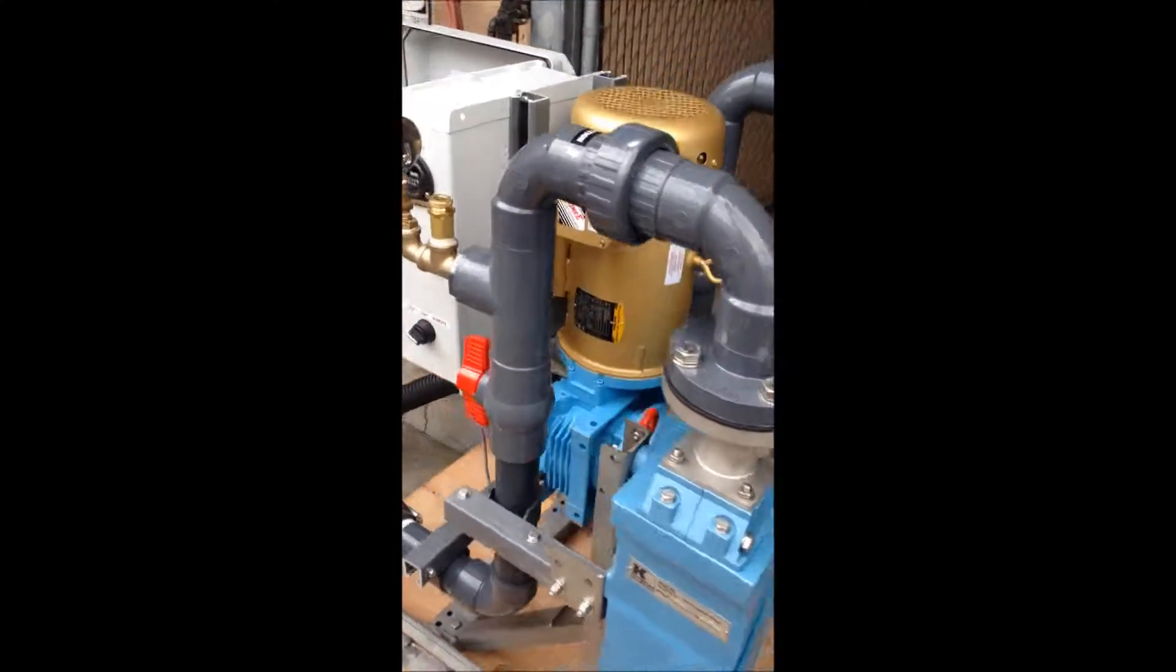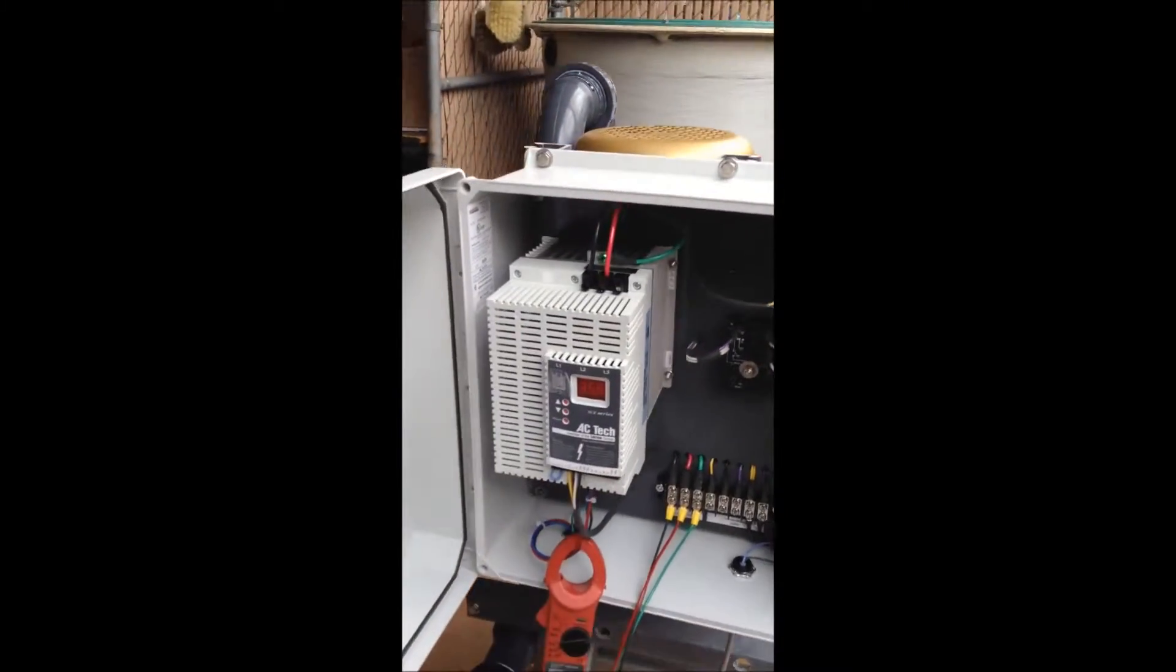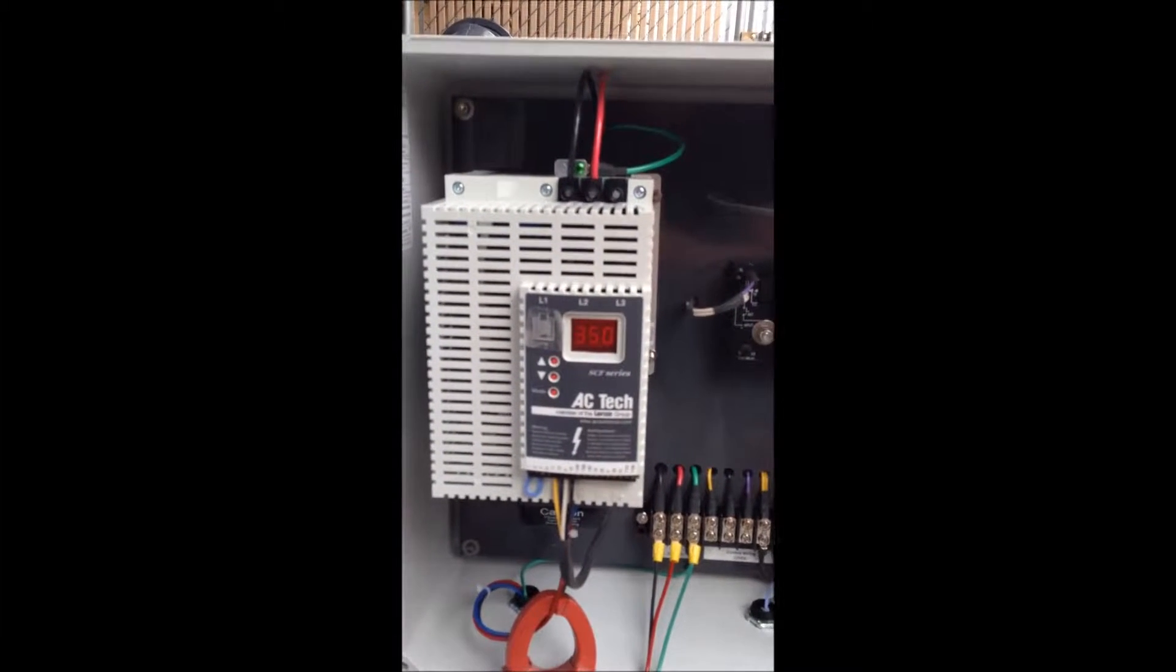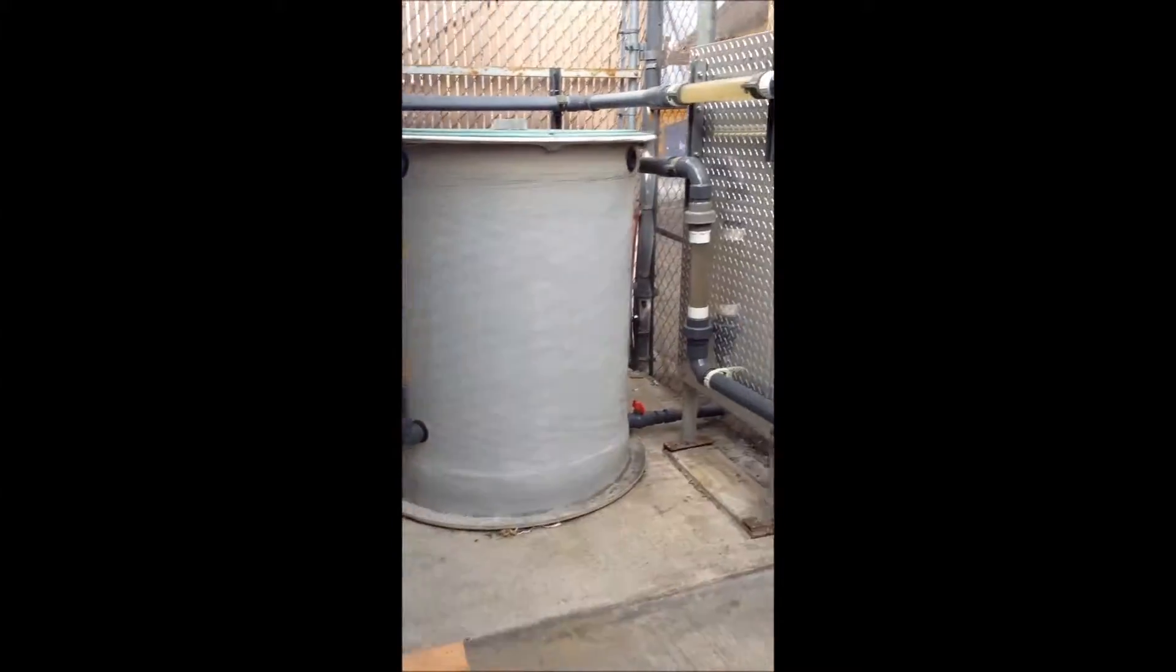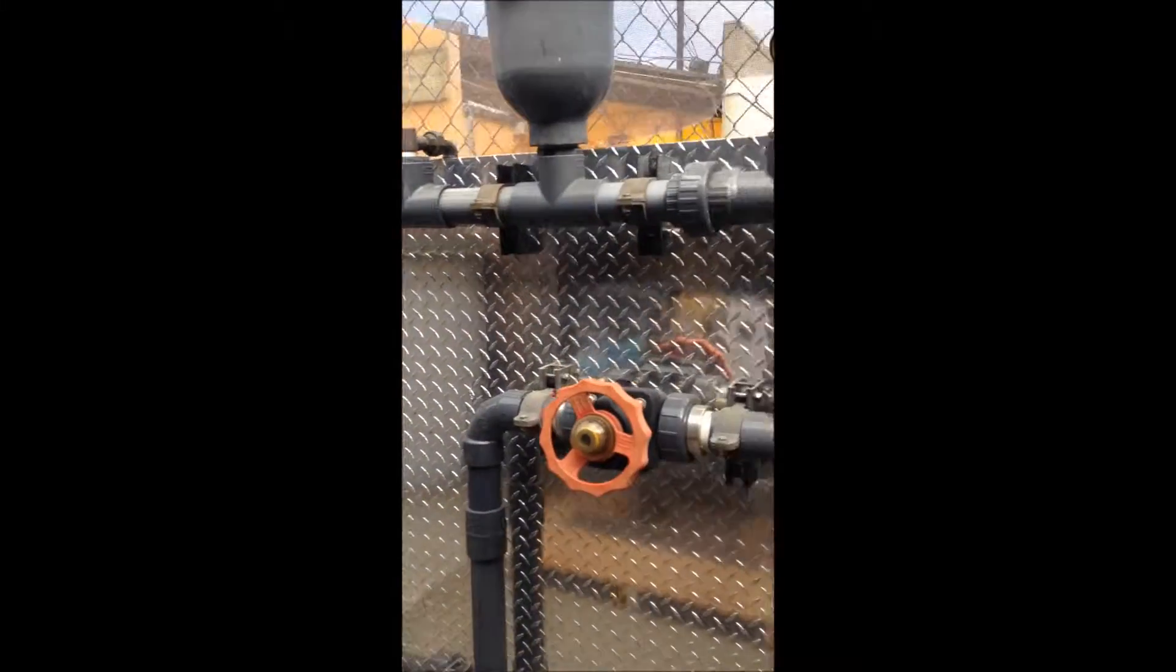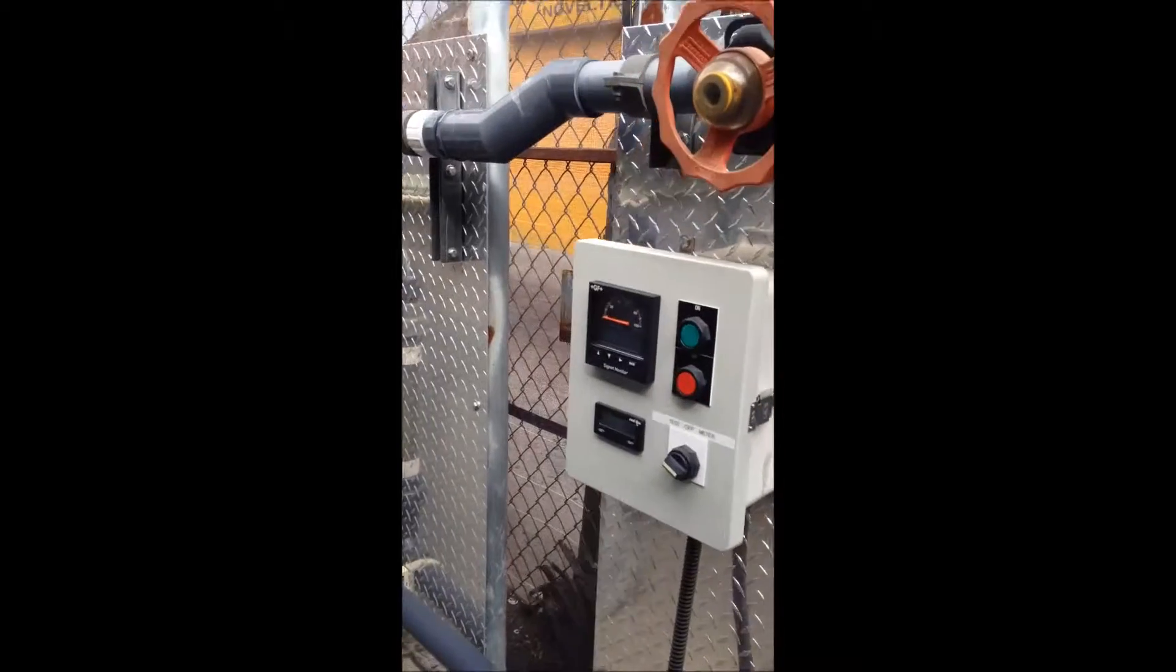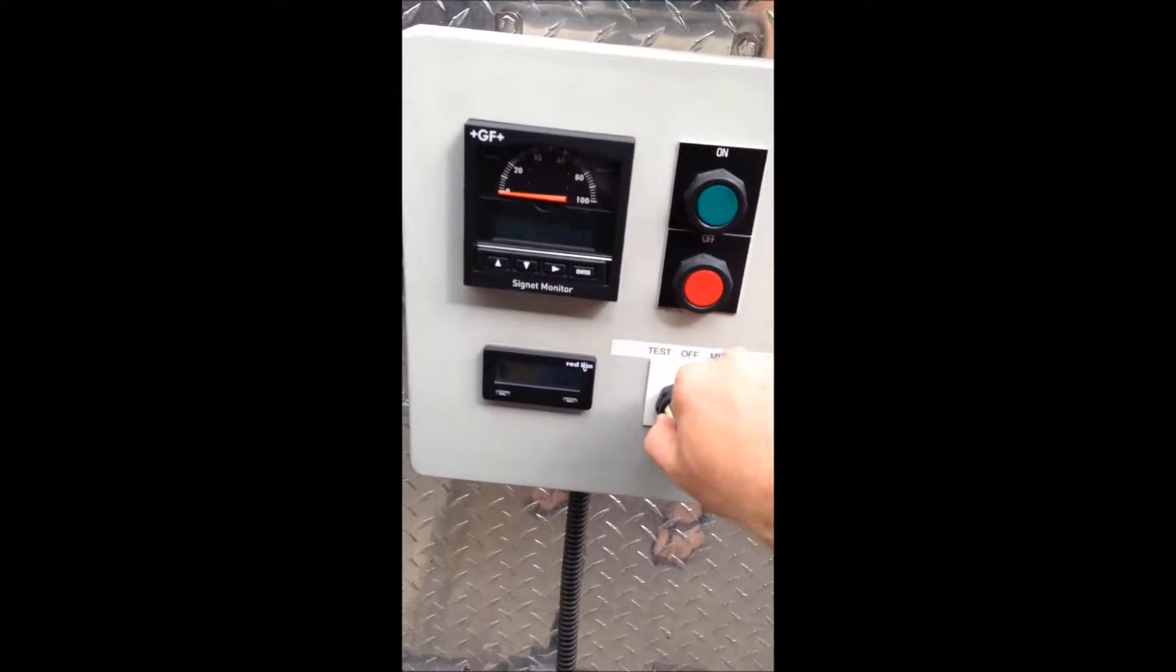We've got the pump slowed down to approximately 35 Hz. This is factory preset and password protected, it cannot be changed in the field without password. This is our testing rack here where we're simulating flows of both vacuum and pressure. We've got our digital flow meter here, which we'll go ahead and turn on for the purposes of our testing.